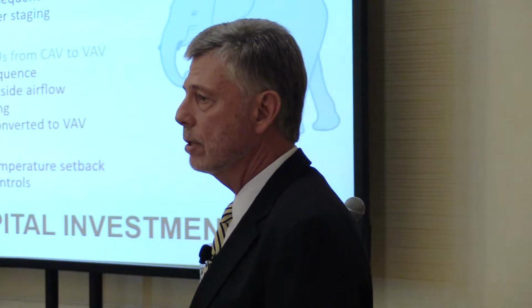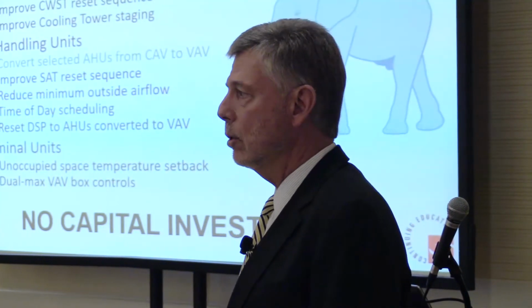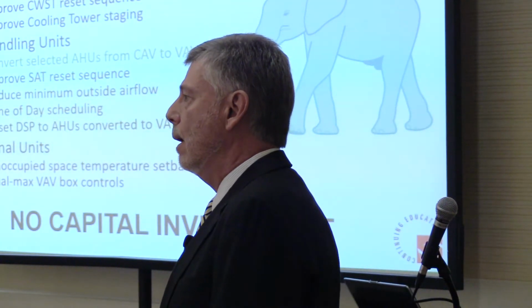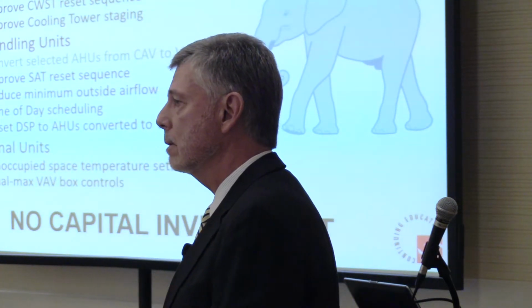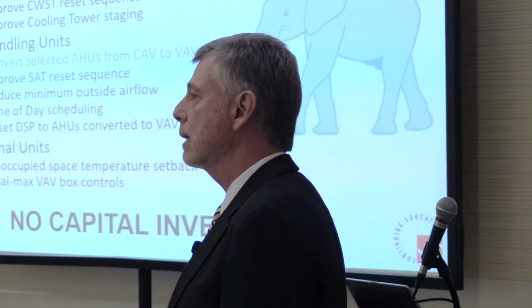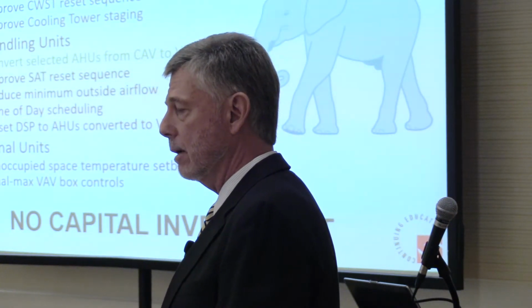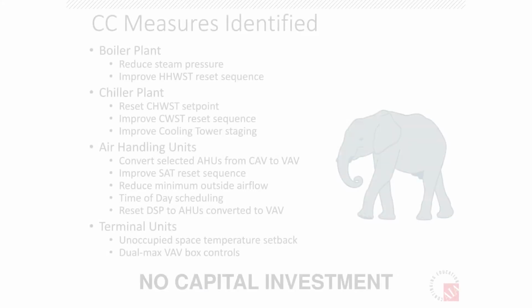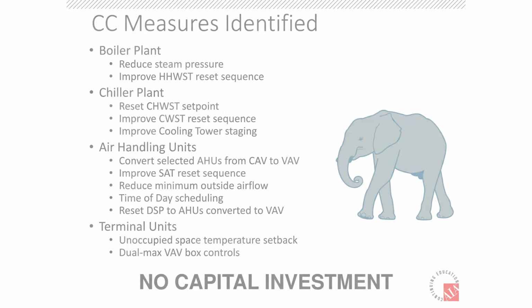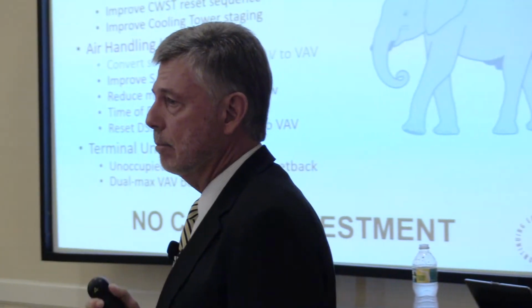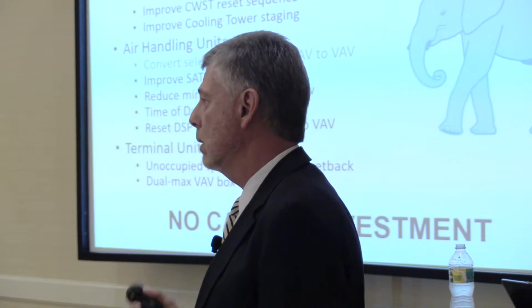One key thing here, as I mentioned earlier, there was no capital improvement or no capital investment, no new equipment. I was talking to someone who approached me just prior to this, and his firm is embarking upon something similar to this, but it sounds like there might be a capital improvement necessary. Hospitals that were designed, I don't know what the magic number is here, but let's say sometime after 2000, probably have a full DDC system controlling every one of those terminal boxes. Those terminal boxes may be actually variable volume boxes operating in a constant volume mode.